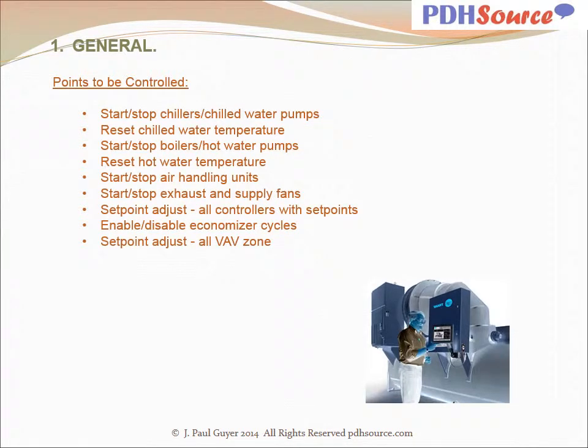Other points to be controlled: start and stop for chillers and chilled water pumps, reset chilled water temperature, start stop boilers, hot water pumps, reset hot water temperature, start stop air handling units, start stop exhaust and supply fans, set point adjustment for all controllers with set points, enable disable economizer cycles, set point adjustment for all VAV zones.